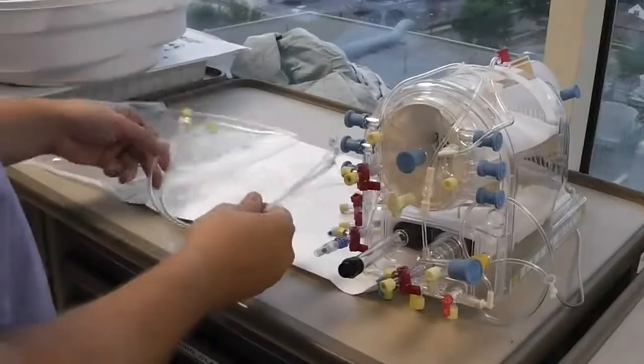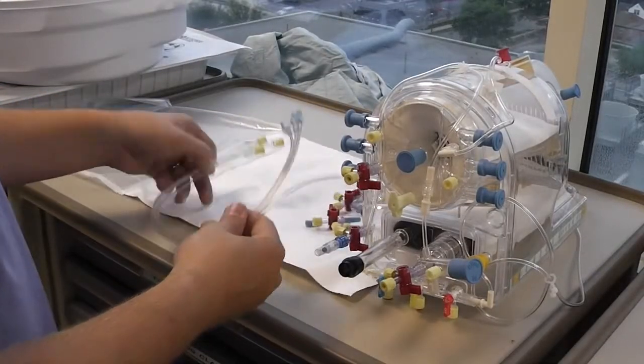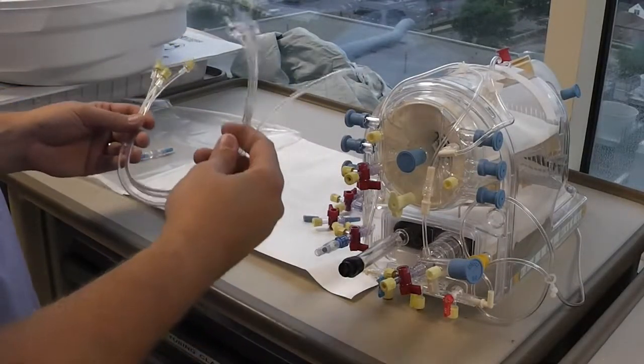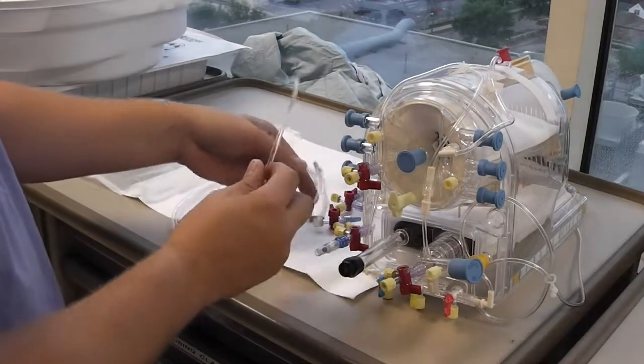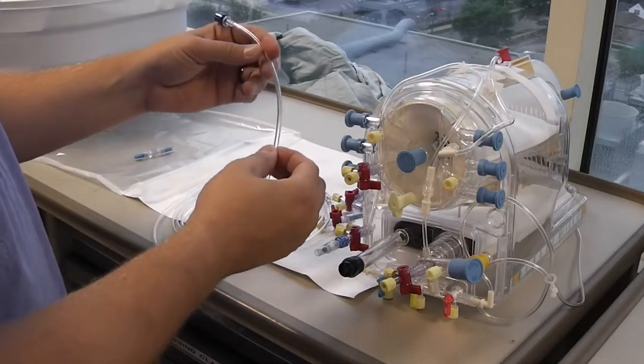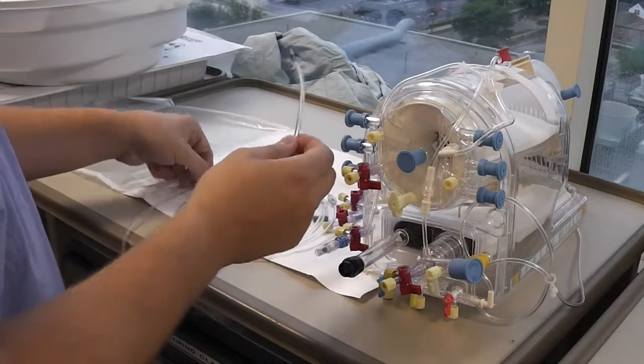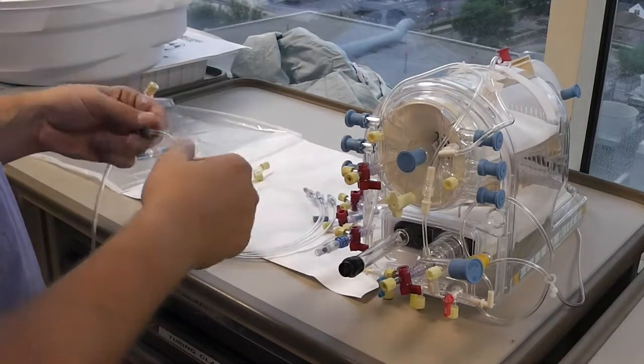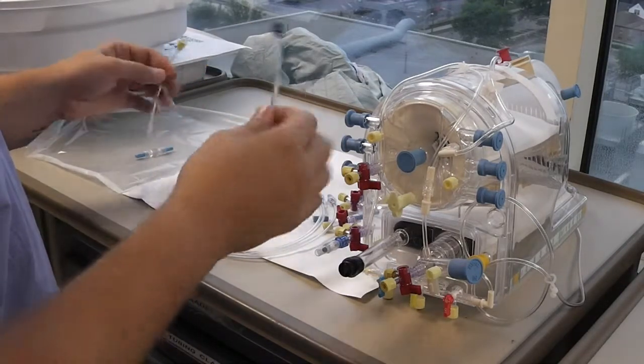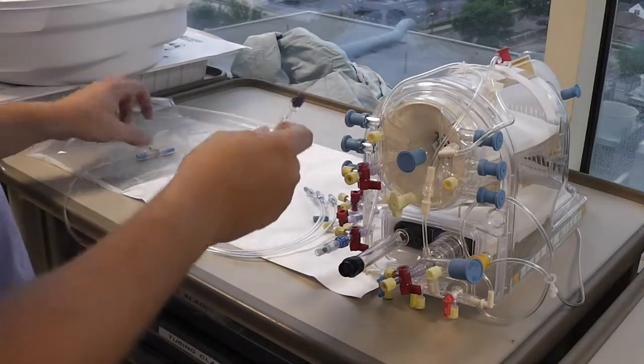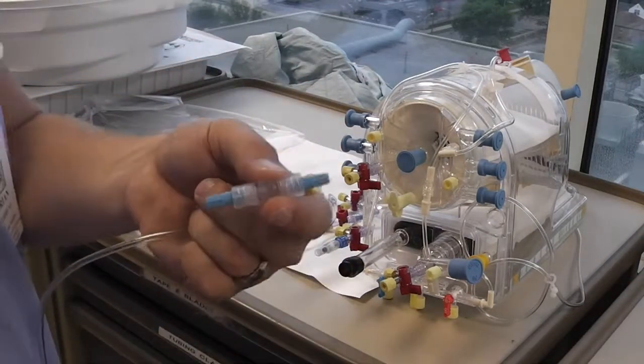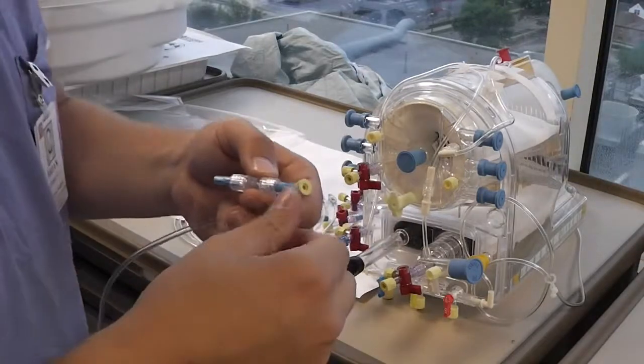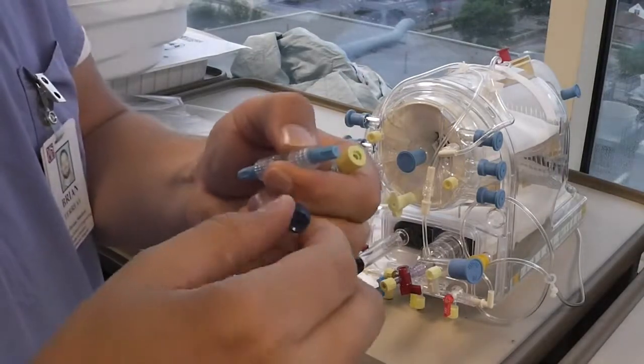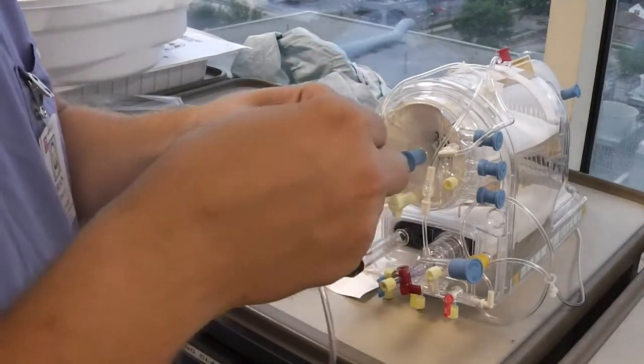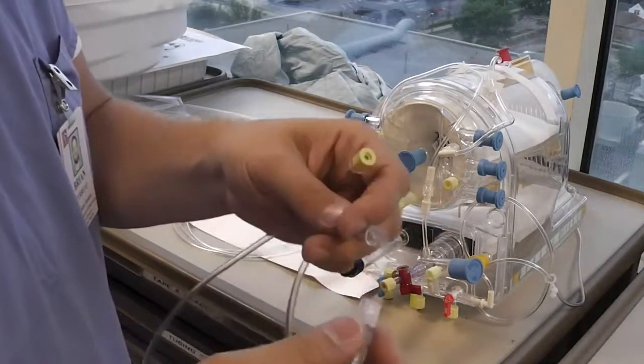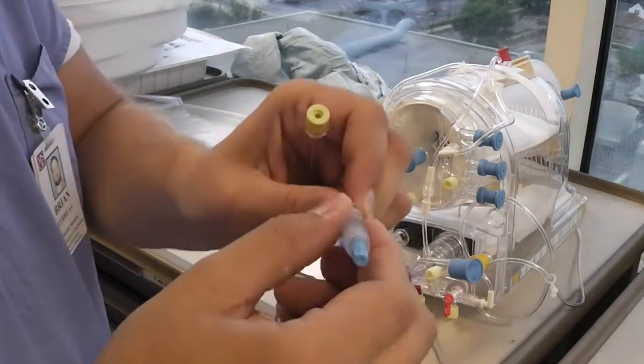Alright, in the pack you'll notice there are 4 lines here. One of them is slightly longer than the other 3, but it's also a larger tubing, and it's a lower durometer. It's a little bit more flexible. This is a low pressure line. You're going to find this double-ended cap in here. Remove one of the caps, doesn't matter which one, and also from the double-ended side, and attach that there.